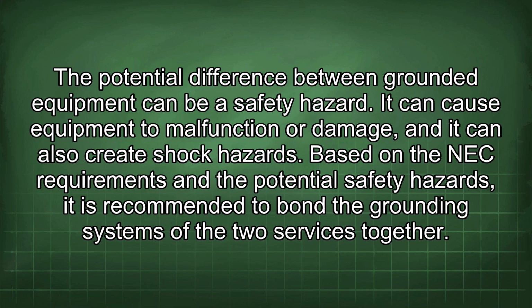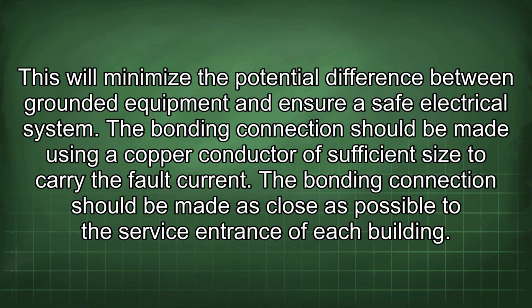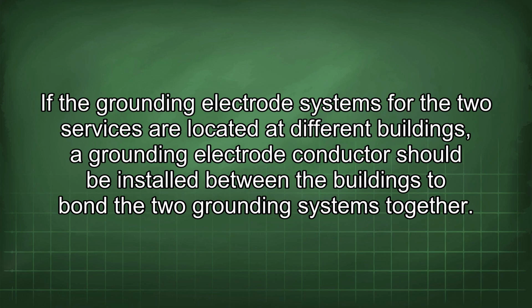Based on the NEC requirements and the potential safety hazards, it is recommended to bond the grounding systems of the two services together. This will minimize the potential difference between grounded equipment and ensure a safe electrical system. The bonding connection should be made using a copper conductor of sufficient size to carry the fault current. The bonding connection should be made as close as possible to the service entrance of each building. If the grounding electrode systems for the two services are located at different buildings, a grounding electrode conductor should be installed between the buildings to bond the two grounding systems together.